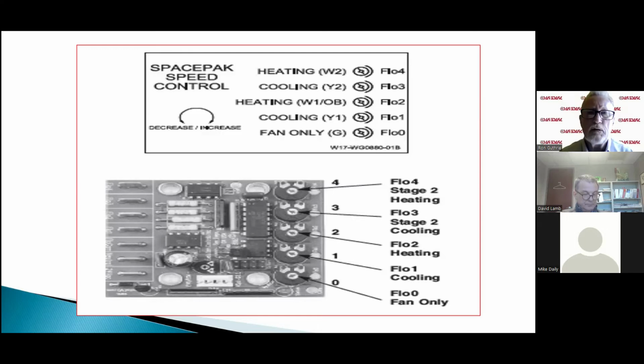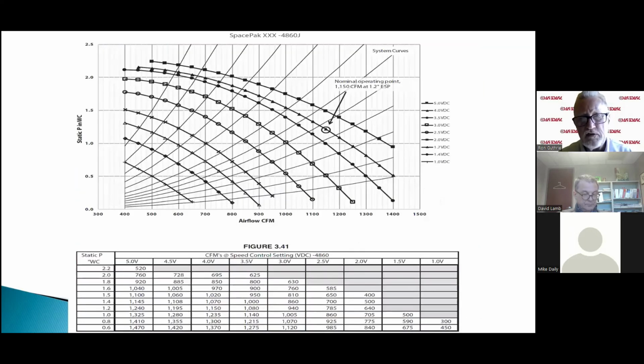Okay, and this is the chart that you would use to determine what volt DC signal you needed to send to the motor head. We've got CFM and pressure. We'd have to look at the two of those and find the spot on the graph that corresponds with both of those, and read the line above it for the volts DC.